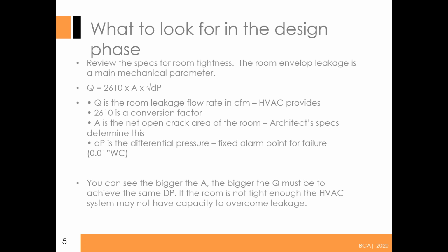So I just want you to see this formula. The bigger the A, the bigger the Q is, to maintain the same DP, which is what typically we have a criteria for. So alarms go off when you get below 0.01 positive in an OR, for example.